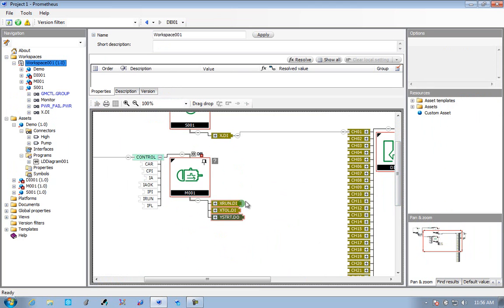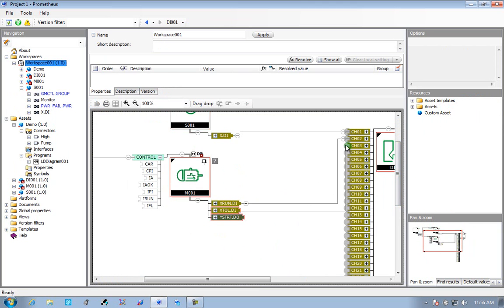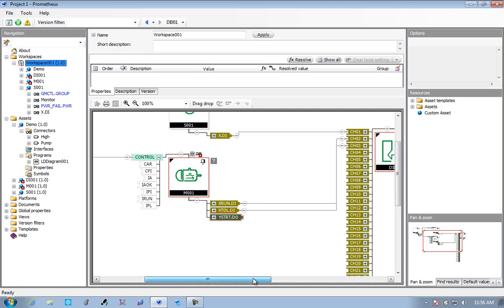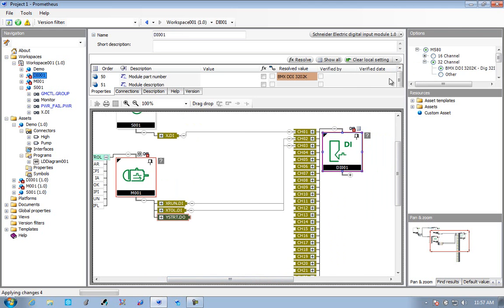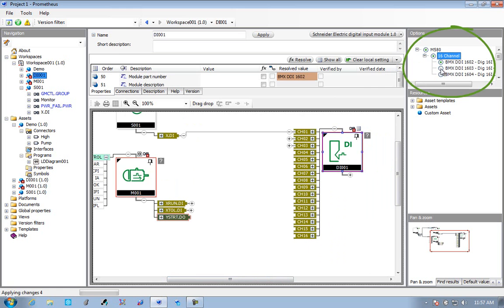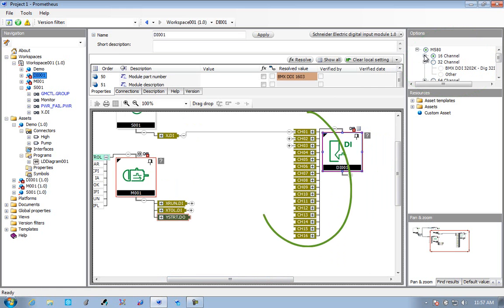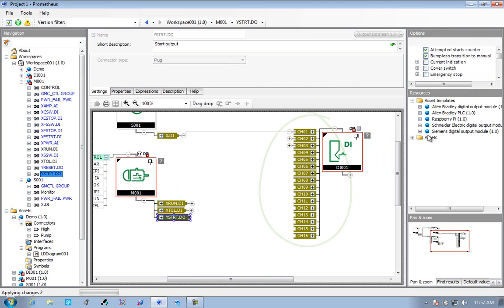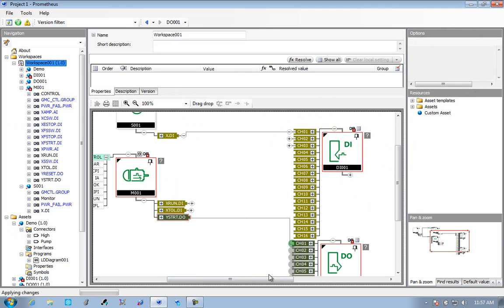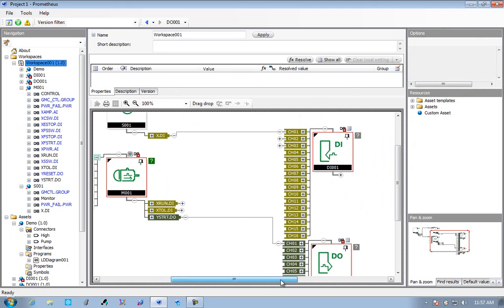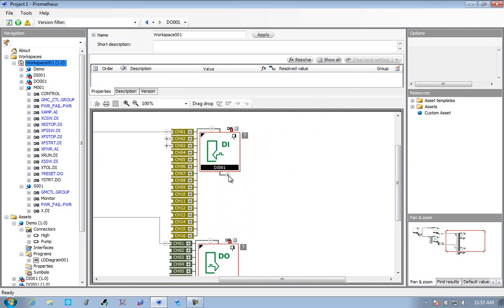Now we're going to wire it to an I.O. module. By wiring to an I.O. module, we're actually committing to a brand. We're saying at this point we're going to deploy to, in this particular case, a Schneider Electric I.O. module. We can just check on the options for this module, which will change the interfaces available to us, as well as changing any of the configuration detail and potentially changing code within the object that's been modified by the option.